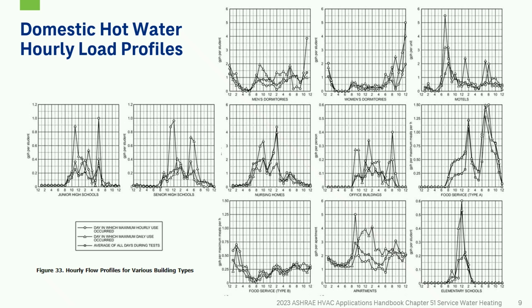Similarly, with the other one, they give 3 scenarios where you could have the average hourly load. You could have hourly loads from the day in which the peak hourly occurred, or you could have hourly loads from the day in which the max daily usage occurred. So if you know that your building may be on the higher end, you can use one of those peak values instead of more of the average value. That would be more holistic of all buildings.